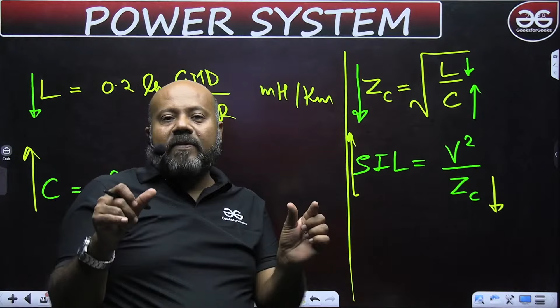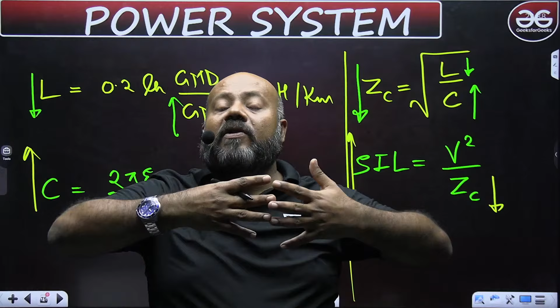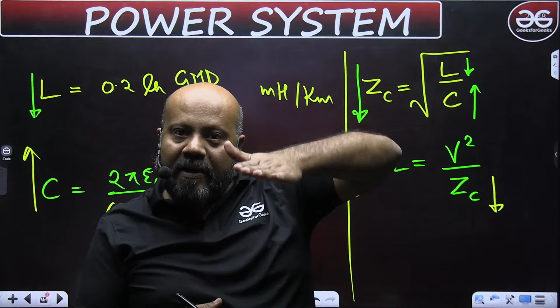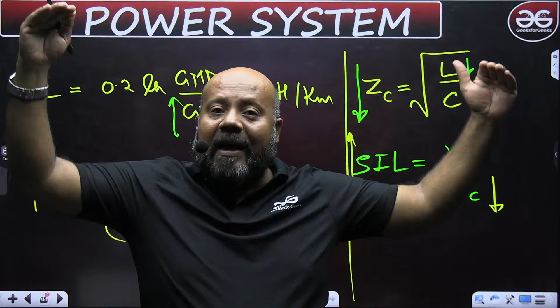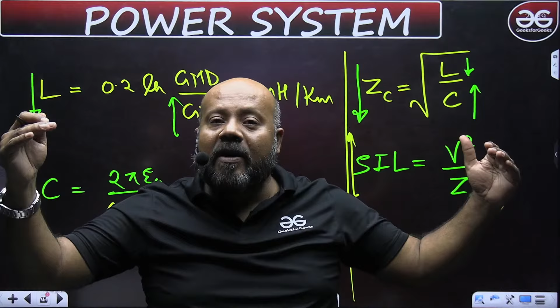See, ACSR conductors, why do we use them? ACSR means steel reinforced aluminum conductor. We use a number of steel strands to increase the tensile strength. If you increase the tensile strength, the sag in the conductor is reduced. The sag being reduced means ground clearance is increased. Ground clearance increased means the height of the transmission tower is reduced. If the height of the tower is reduced, the overall cost is reduced.